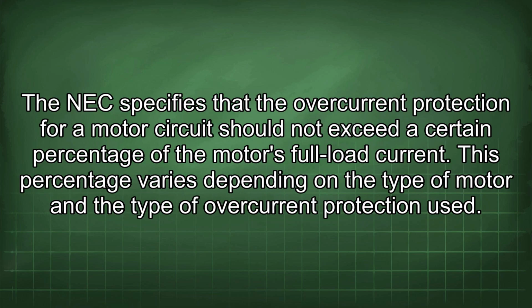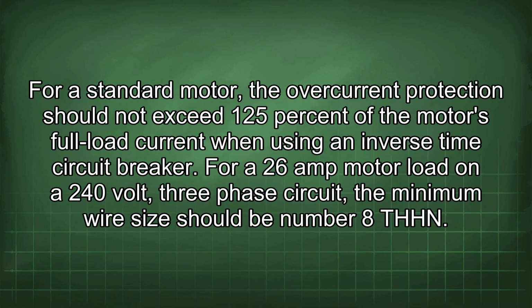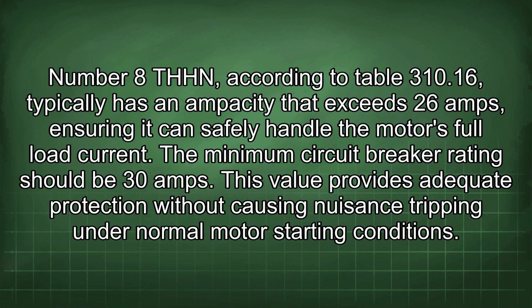The NEC specifies that the overcurrent protection for a motor circuit should not exceed a certain percentage of the motor's full load current. This percentage varies depending on the type of motor and the type of overcurrent protection used. For a standard motor, the overcurrent protection should not exceed 125% of the motor's full load current when using an inverse time circuit breaker. For a 26 amp motor load on a 240 volt, three-phase circuit, the minimum wire size should be number 8 THHN. Number 8 THHN, according to Table 310.16, typically has an ampacity that exceeds 26 amps, ensuring it can safely handle the motor's full load current.